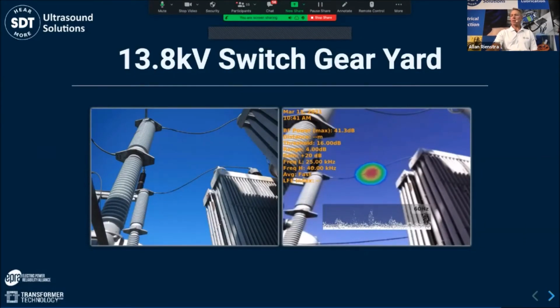Here's one more - this is a 13.8 kV switchgear yard, with a cable running from the transformer over to an insulator, and we've got some bird caging going on right here. That breakdown of the insulation is producing a source of airborne corona, which we were able to pick up with our parabolic dish.